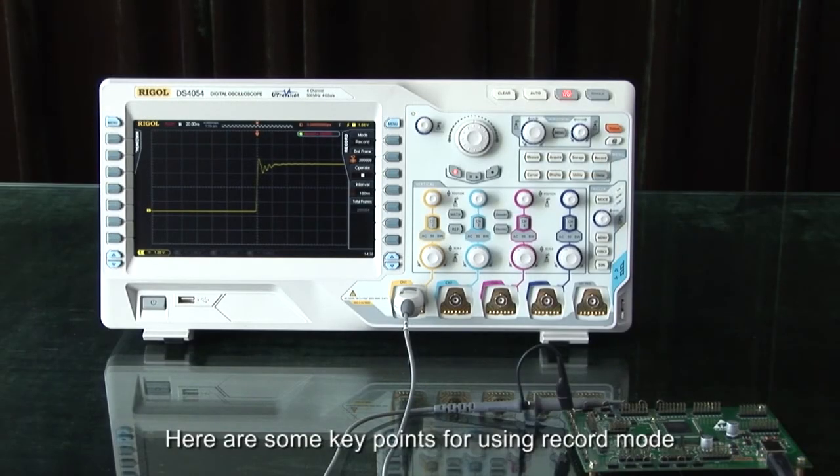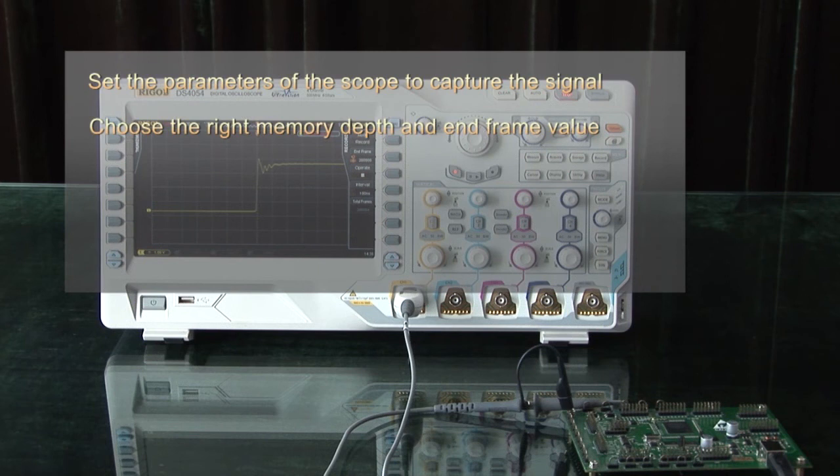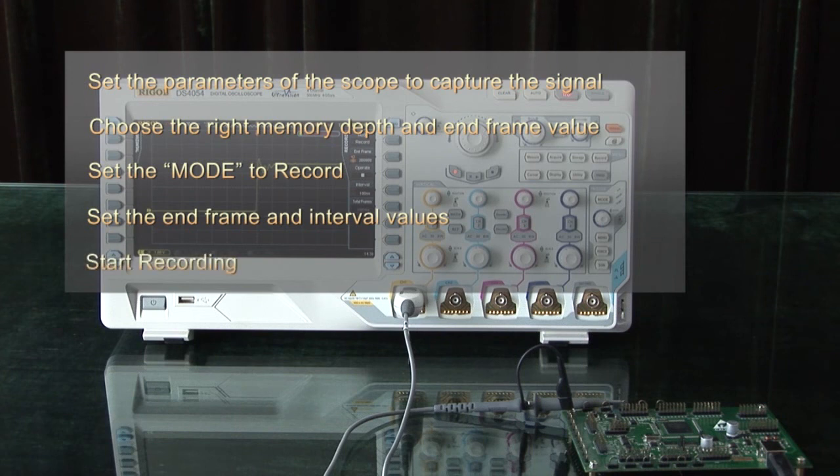Here are some key points for using record mode. Set the parameters of the scope to capture the signal. Choose the right memory depth and end frame value. Set the mode to record, set the end frame and interval, and then start recording.